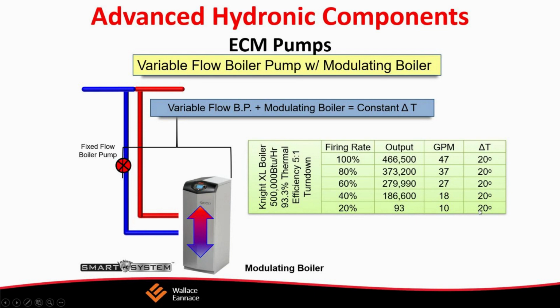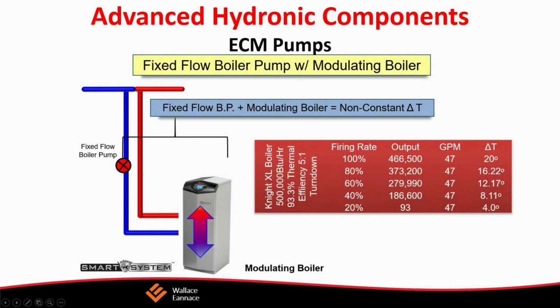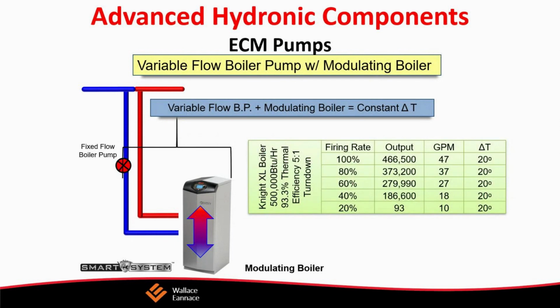At an 80% firing rate, we'd have 373,000 BTUs, but we would still be moving the water at 47 GPM. The delta T would then drop to 16.22. At 60%, 280,000 BTUs goes out, and it puts a delta T of approximately 12 degrees. Then just to take a look at 20%, the output is 93,000 BTUs. It's only going to have a 4-degree delta T.